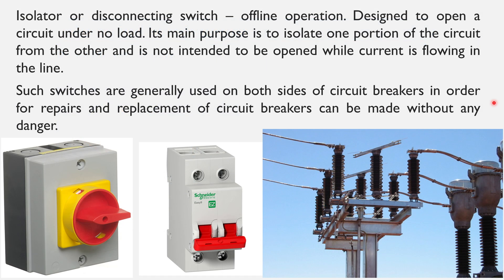An isolator or disconnecting switch is mostly used in offline operation. It is designed to open a circuit under no load — its main purpose is to isolate one portion of the circuit from another and is not intended to be opened while current is flowing. Here I have a short video of a 345,000 volt switch opening, and you can see the significant arc produced.